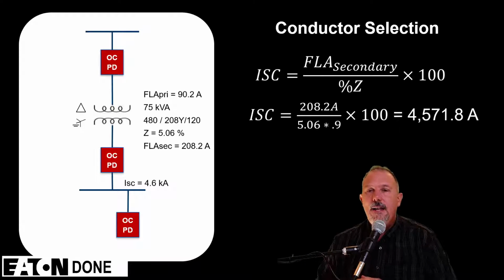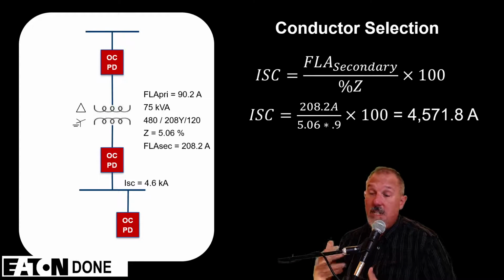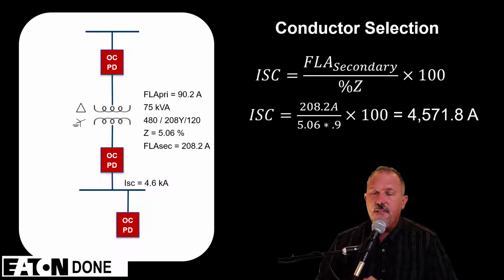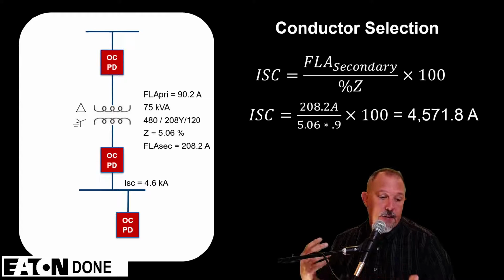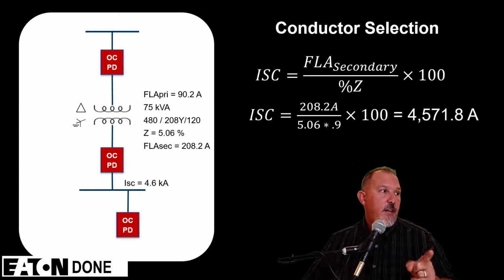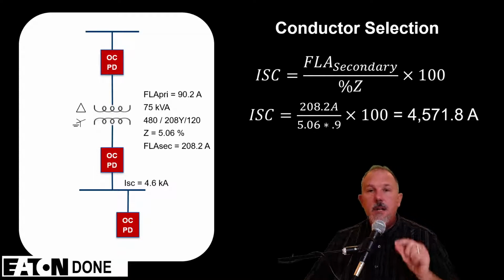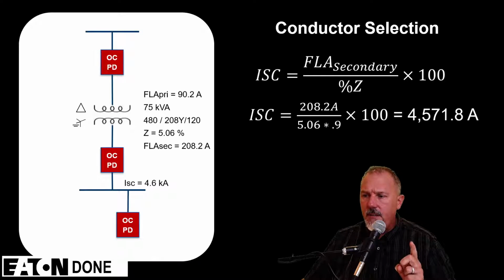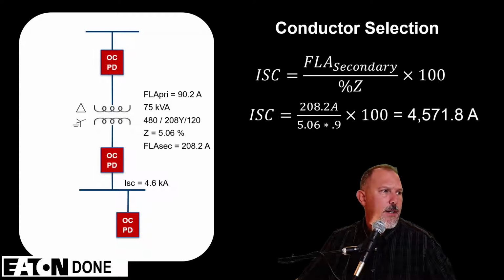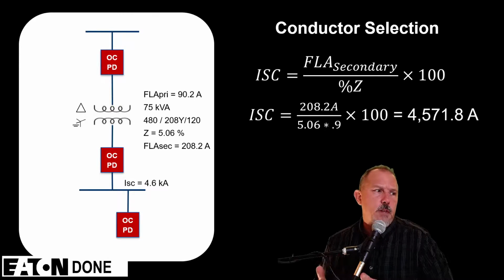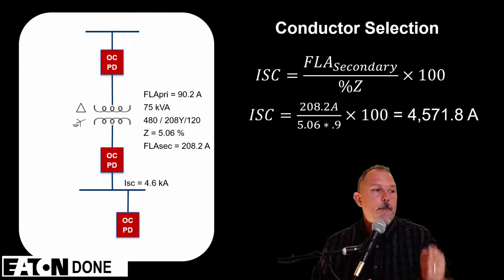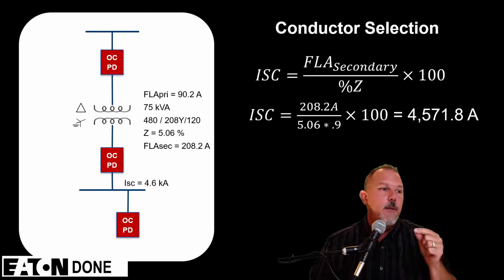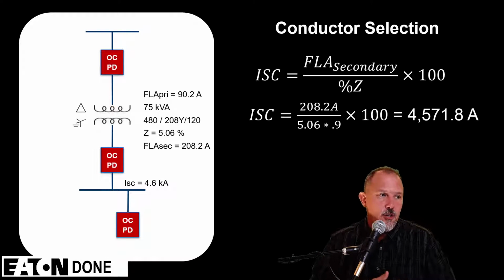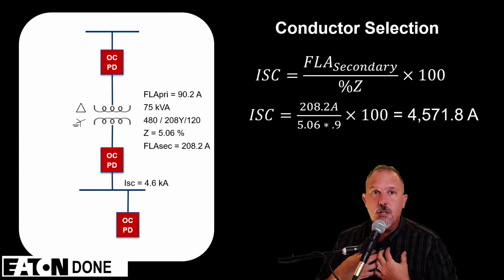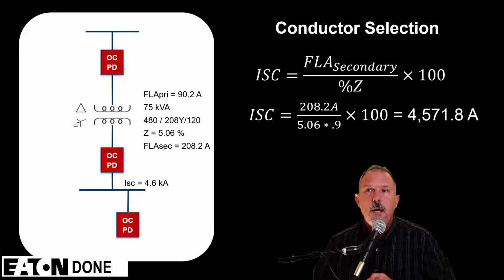multiply all of that by 100, and I get a maximum possible fault current you could possibly see, assuming the low end of the impedance on that transformer, of 4,571.8 amps. And if I look at IEEE 1584, it tells me the minimum number that they use, and I believe I had it open. Yeah, I do. It's right here. Section 4.3 of IEEE 1584 2018 tells us that sustainable arcs are possible, but less likely in three-phase systems operating at 240 volts nominal or less with an available short circuit current of less than 2,000 amps. Our available short circuit current at the secondary maximum is 4,571.8 amps.